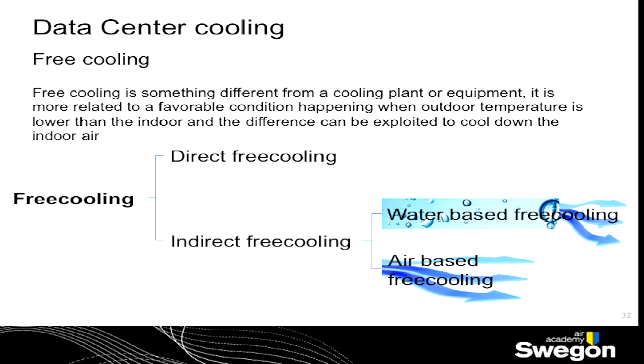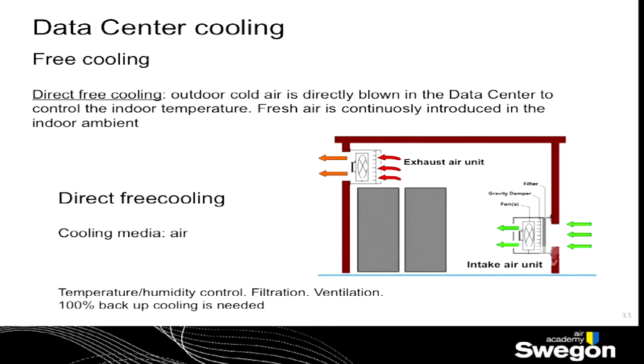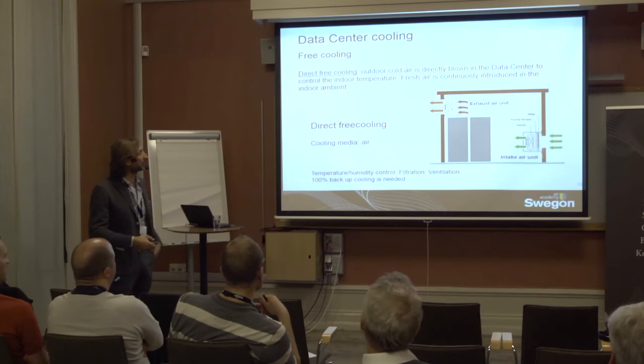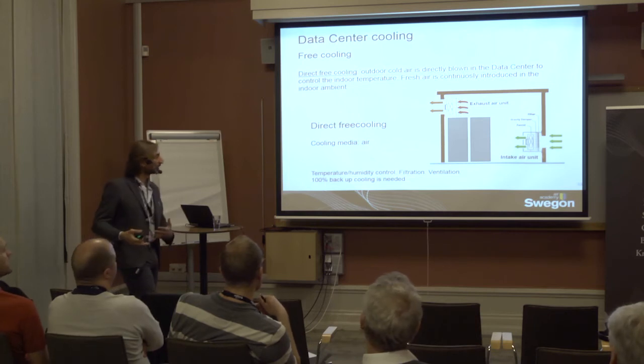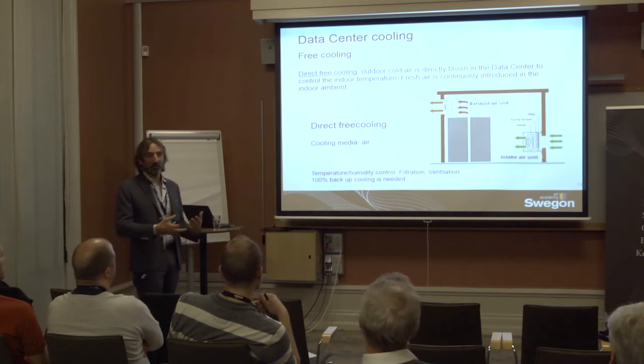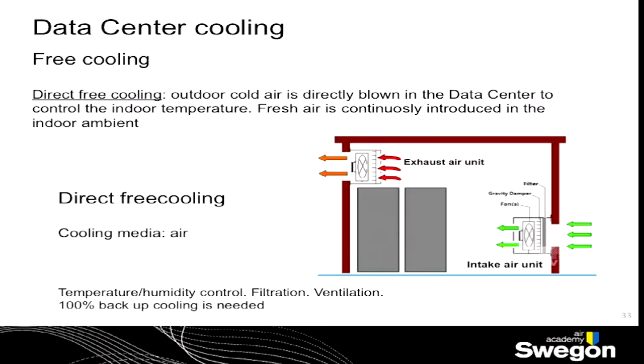If we go to the free cooling instead, we have to divide between direct and indirect, which is the main difference. The main difference is that if you use a direct free cooling system, you have to accept that fresh air is introduced in the data center. And this is, of course, a limitation, because the fresh air takes with itself the pollutant. You can filter, of course, but you can have a very efficient filter, but it costs in terms of pressure losses. And of course, you cannot avoid introducing humidity. You have not a strict control on the indoor conditions.